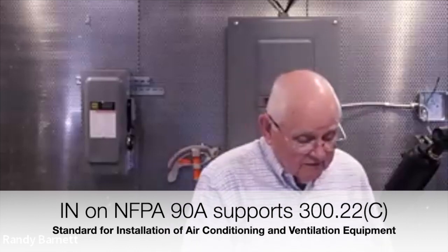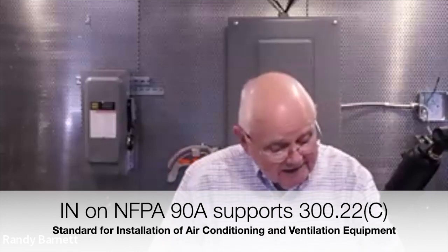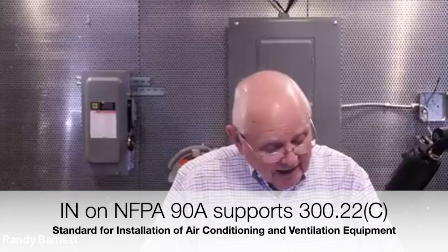300.22(C) is wiring and ducts not used for air handling, fabricated ducts for environmental air, and other spaces for environmental air, what we call plenum. So for example, that is what this NFPA 90A is talking about. Okay, so I have two places where it's going to give me specific information for the conductor types, insulation, cable ties, and whatnot that I can use. Where? Under floor in my ventilation spaces, and above that suspended ceiling overhead.